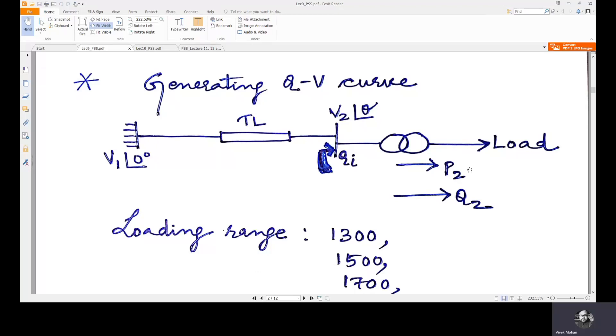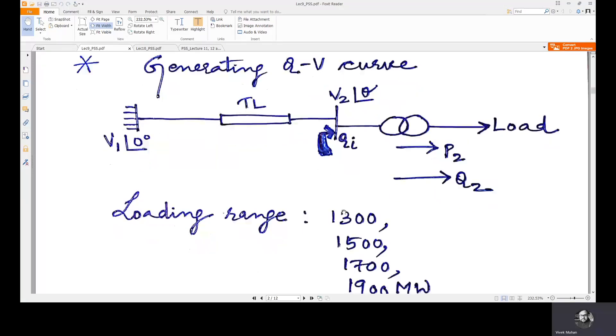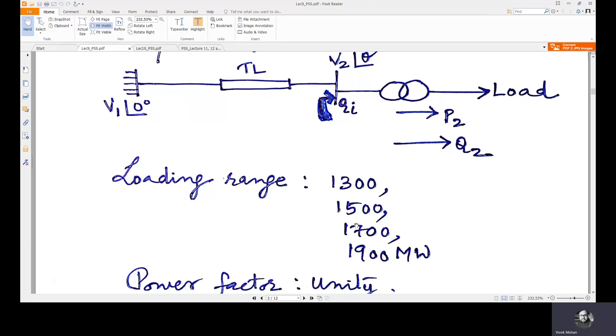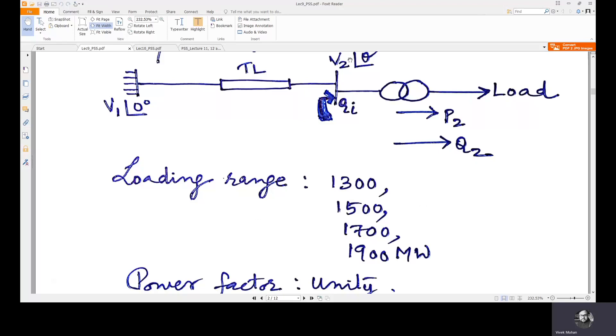The active and reactive power consumed by the load are represented by P2 and Q2. We have several loading ranges for this case study: 1300, 1500, 1700, and 1900 megawatts, with unity power factor assumed. Whenever the voltage goes down due to increased reactive power consumption from the load side, the reactive power compensation device increases its injection accordingly.